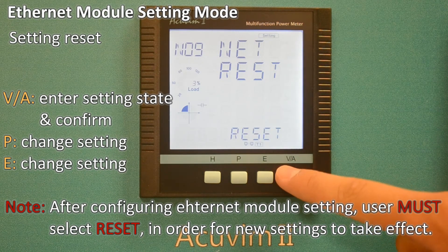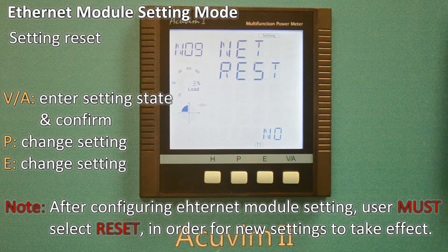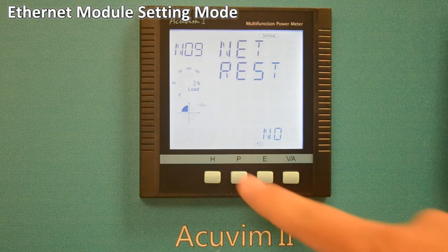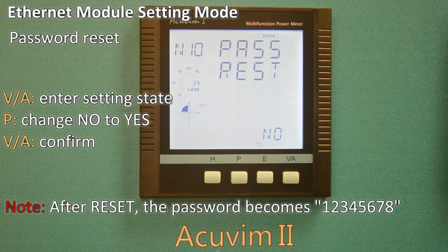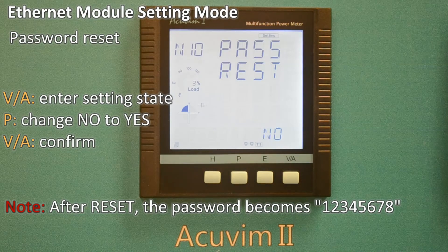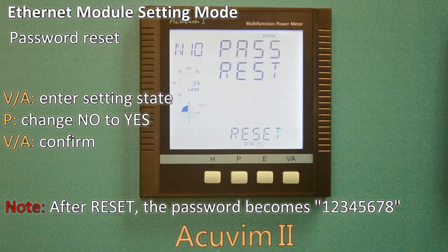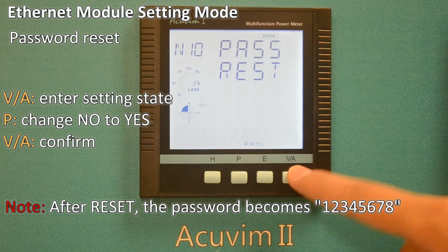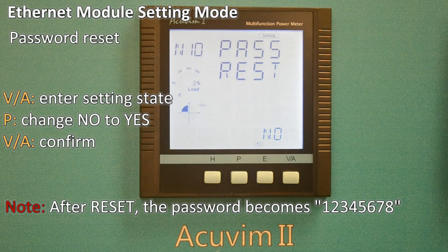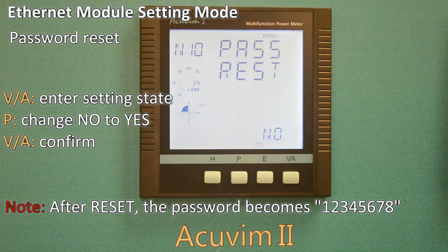Pressing the VA key will confirm these settings. In the last screen, you can reset the axm-net module's password. To reset the password, press VA, then P, then VA again, and the password becomes 12345678.